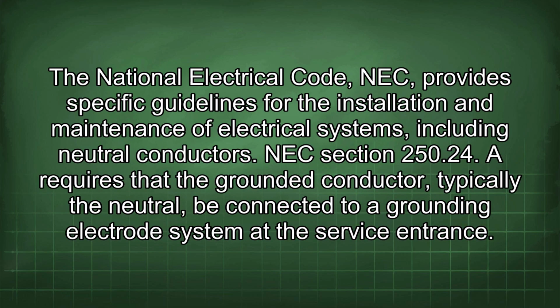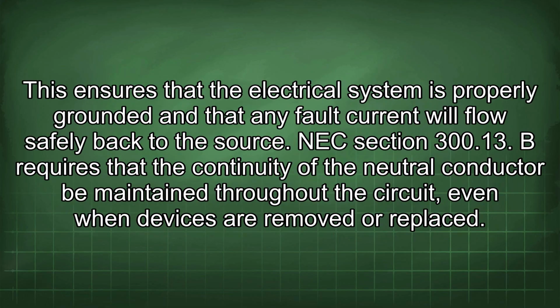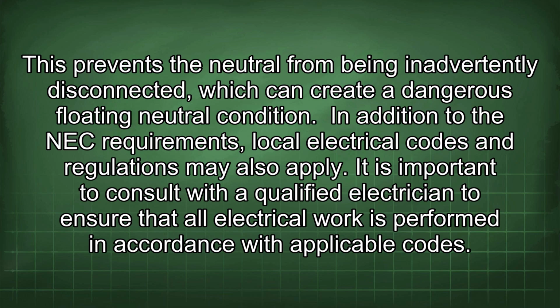The National Electrical Code, NEC, provides specific guidelines for the installation and maintenance of electrical systems, including neutral conductors. NEC Section 250.24 requires that the grounded conductor, typically the neutral, be connected to a grounding electrode system at the service entrance. This ensures that the electrical system is properly grounded and that any fault current will flow safely back to the source. NEC Section 300.13(B) requires that the continuity of the neutral conductor be maintained throughout the circuit, even when devices are removed or replaced. This prevents the neutral from being inadvertently disconnected, which can create a dangerous floating neutral condition.